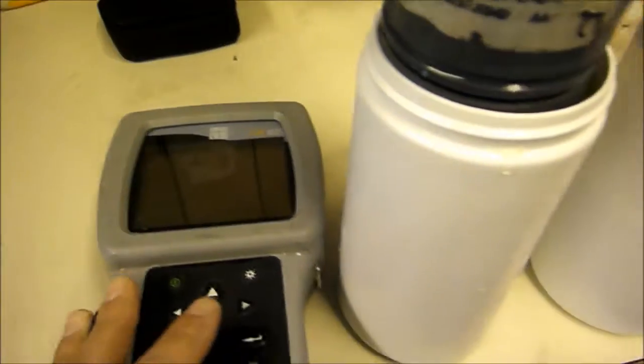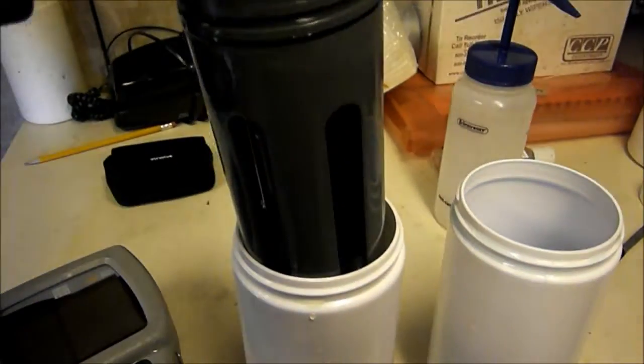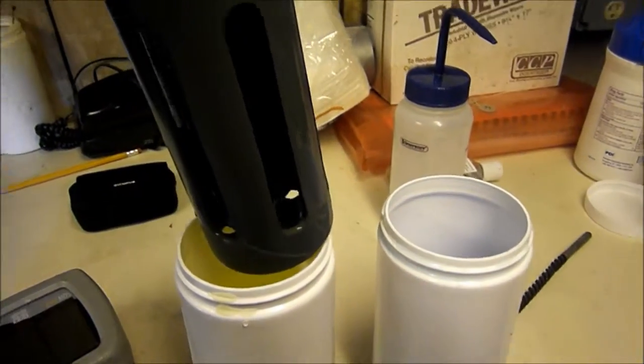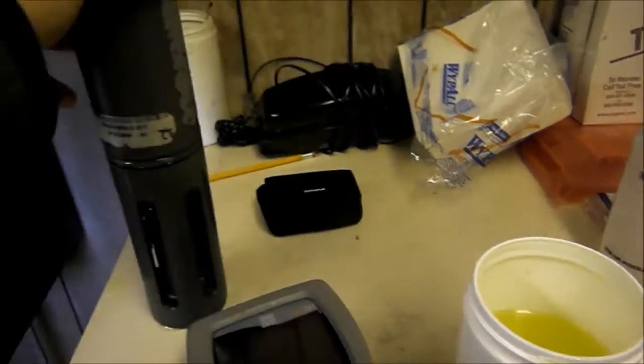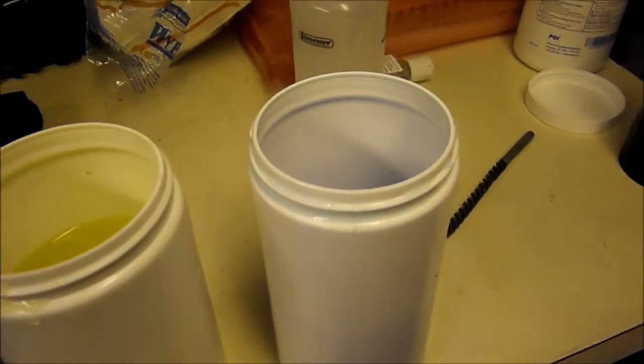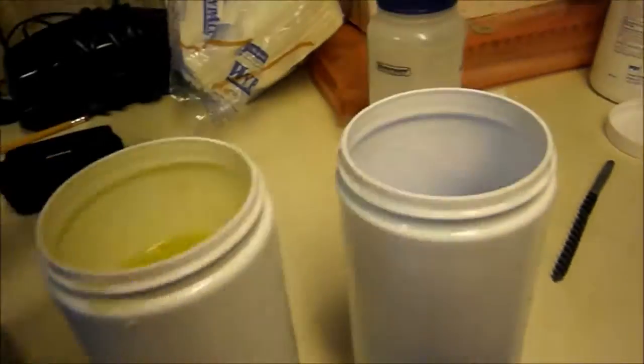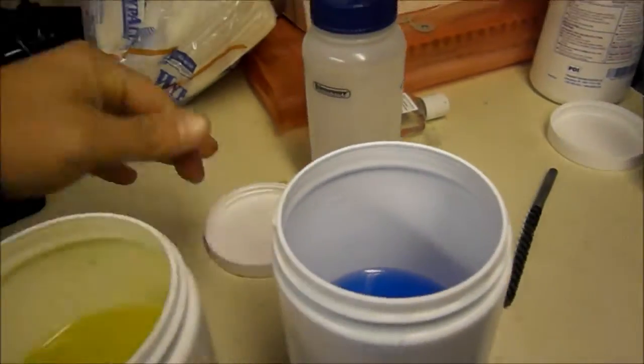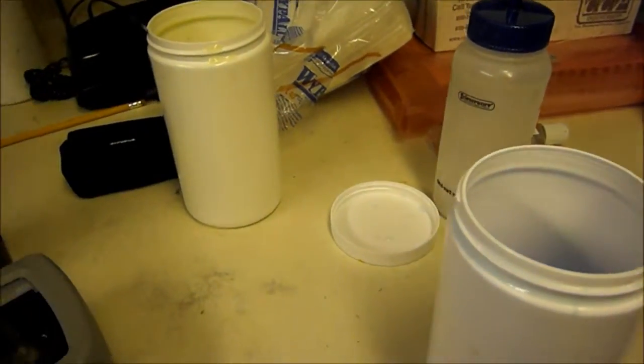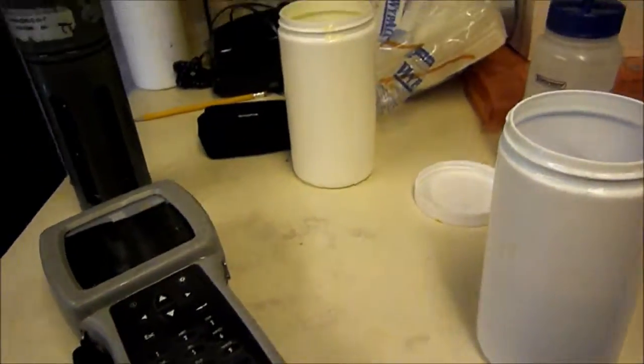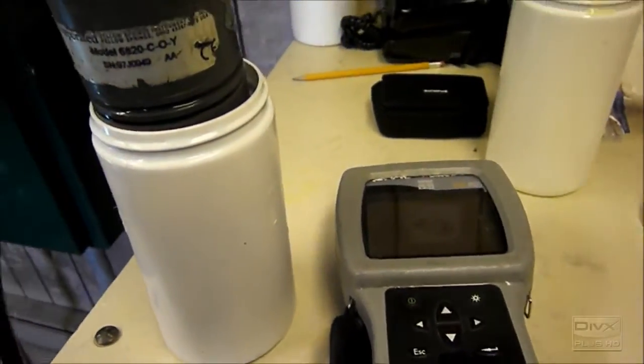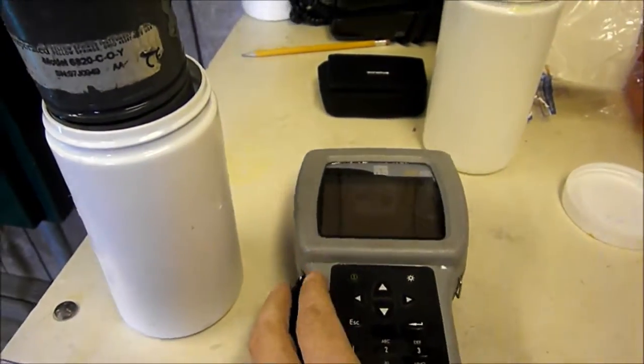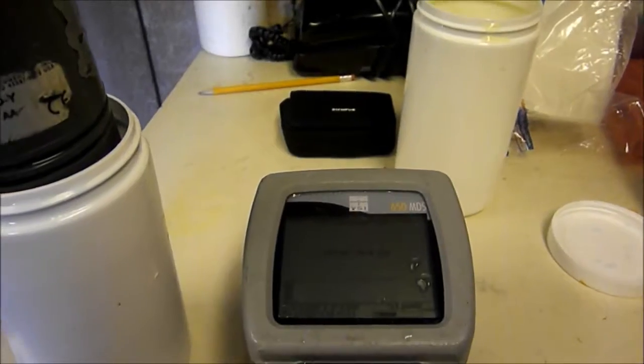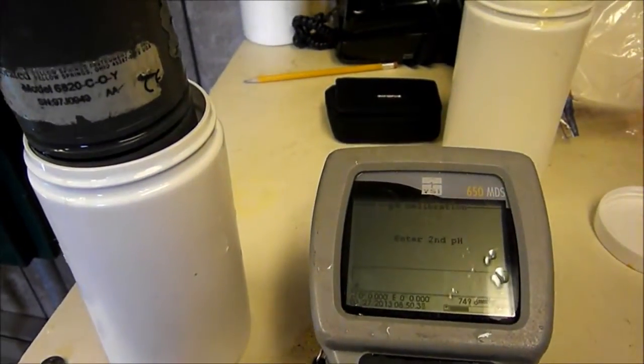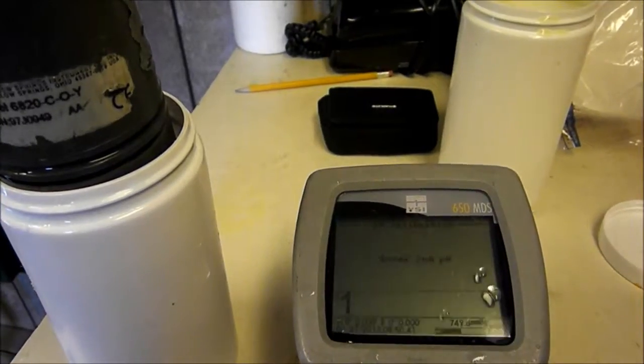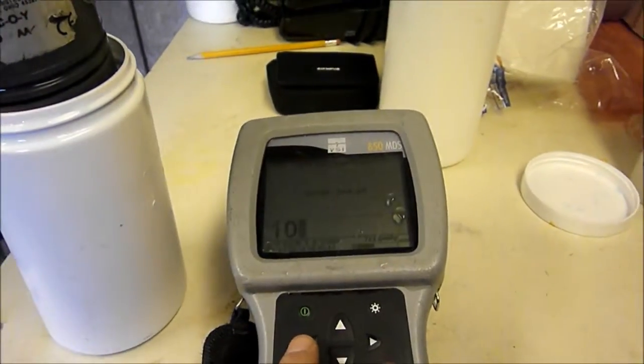Now your second pH. Right here is where you'd want to rinse off your sonde properly with water and even some pH 10 solution, but we don't have that available right now, so I'm going to try to wipe it off as much as possible. Okay, so I got all that pH 7 solution off of there, or as much as I possibly could. It's asking for the second pH point, which is 10. Go ahead and hit enter.